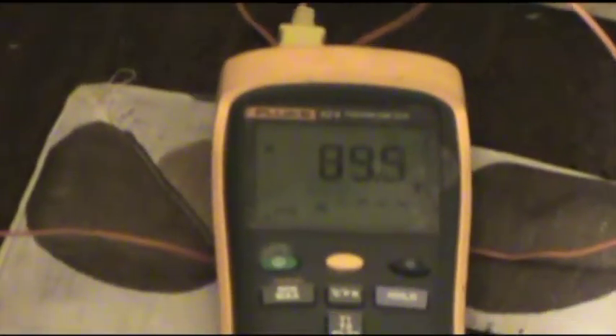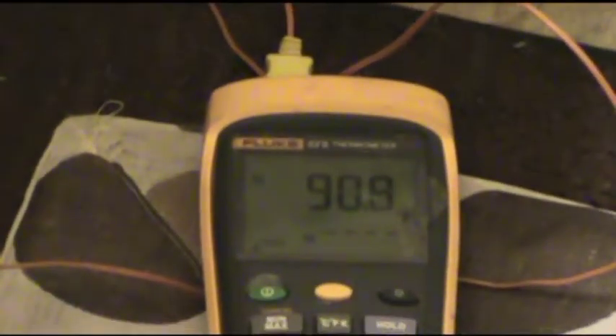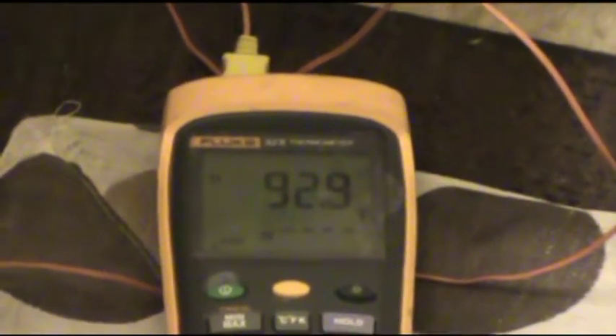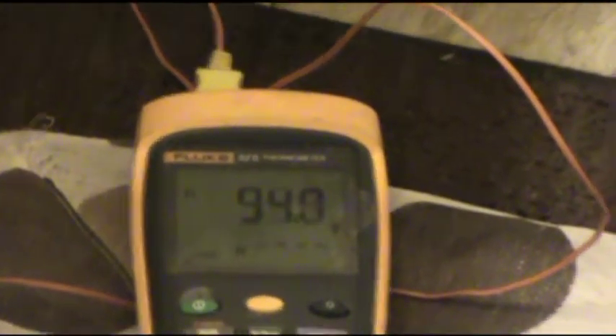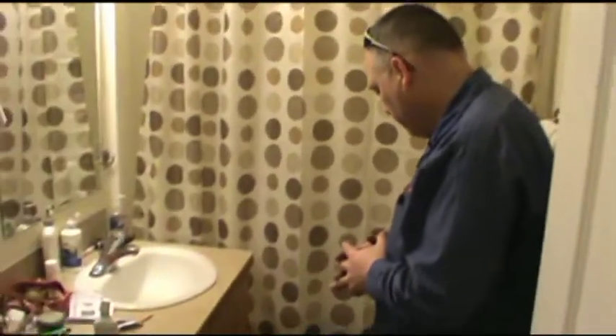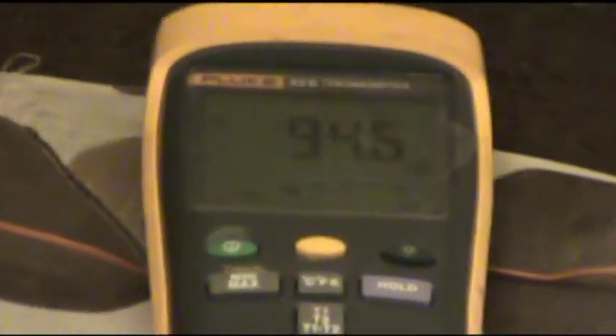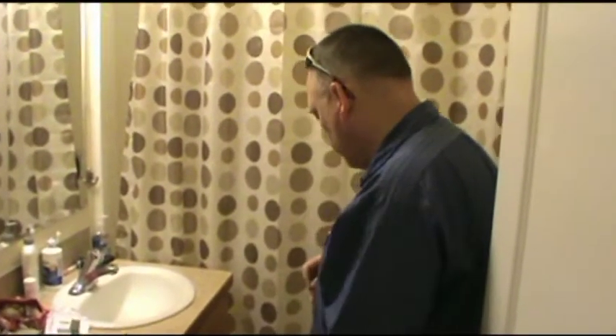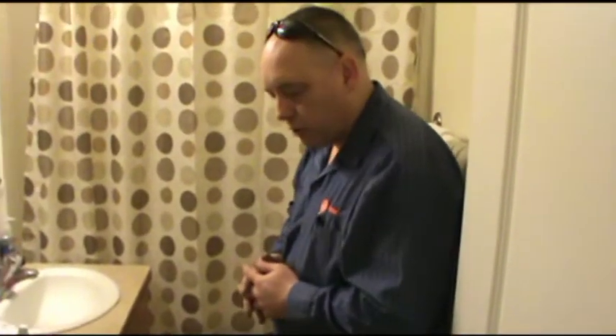And we should see about a 25-degree temperature difference, maybe a little bit more than that with these outside air temperatures. So if you take your 71 and you add 25, we should settle out somewhere in the mid-90s. Actually mid to upper 90s because we're a little bit warm outside, so we should probably be somewhere between 95 and 100. And I think we're going to settle out right there. Again, the longer the machine runs, the more it'll build towards higher performance. So we're reading almost 95 degrees right now, which is really close to the numbers I'm expecting to see. So I am now satisfied that this machine is heating well and that it is charged correctly.